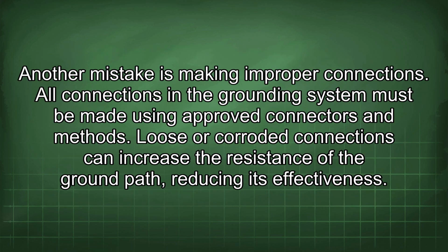Another mistake is making improper connections. All connections in the grounding system must be made using approved connectors and methods. Loose or corroded connections can increase the resistance of the ground path, reducing its effectiveness.